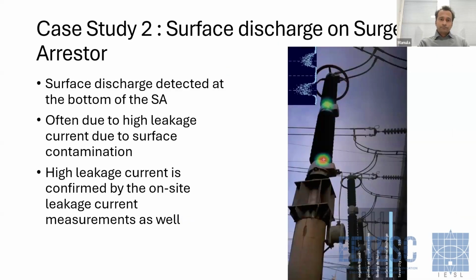And then in our second case study, we have this surge arrestor in this high voltage substation. So in this case, the partial discharge is happening not from the high voltage end, but from the intermediate and the earth potential level as well. This is a kind of thing that can happen in surge arrestor equipment because of the voltage or the electrical field stress gradient. That would be caused by the leakage current most often, which is due again to the contamination of the external surface of this surge arrestor.